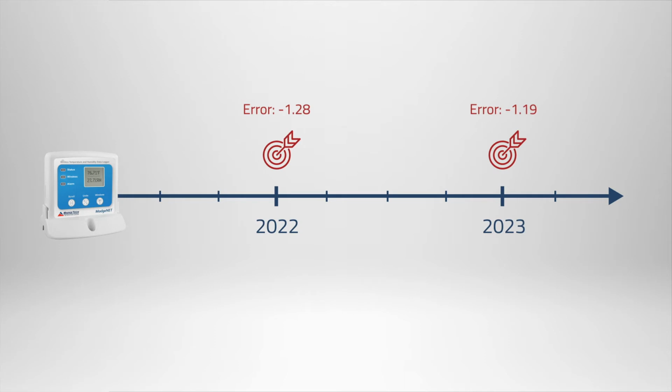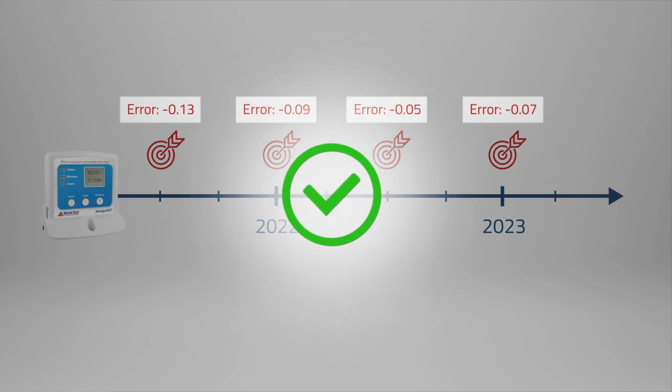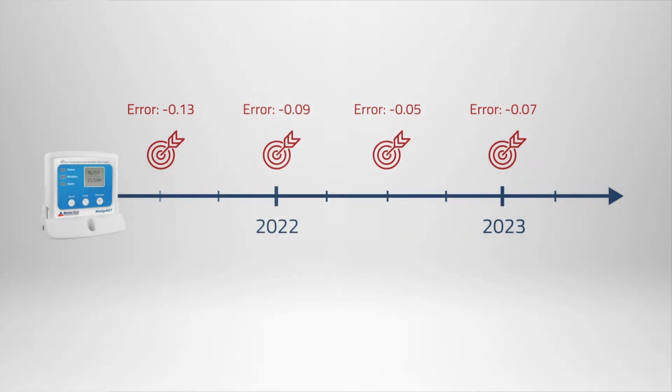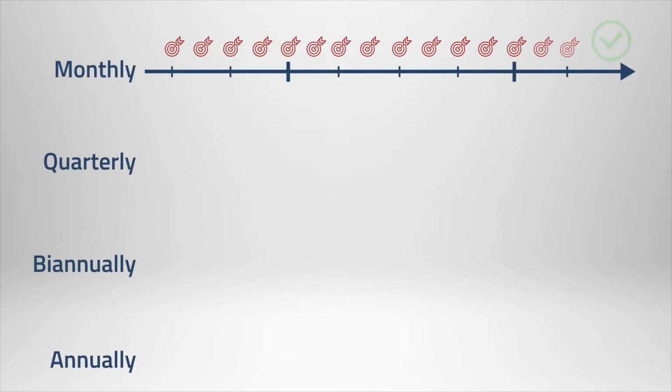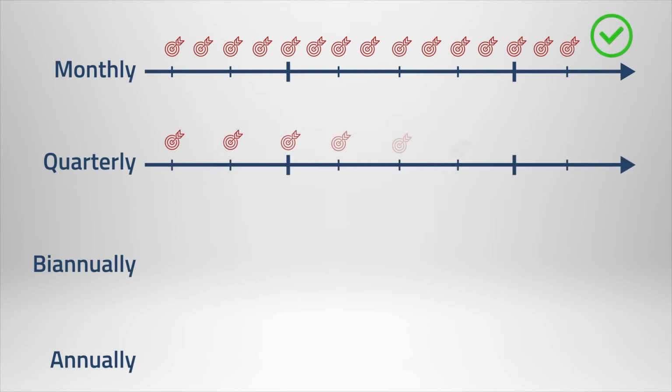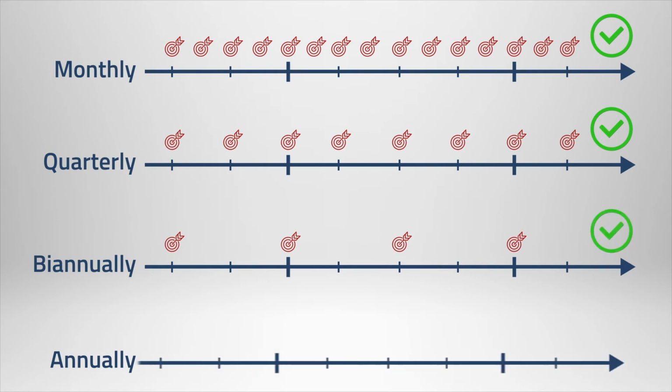Based on the extent of deviation, instead of annual calibrations, we decide to try every 6 months. If after the next calibration, 6 months later, the device error is acceptable, we'll continue utilizing this new interval. If not, we'll continue this process until the deviation is within a tolerable range. If risk mitigation of device accuracy is absolutely vital, we may recommend beginning with a shorter calibration interval and expanding from there, so long as calibration integrity remains within an acceptable range along the way.